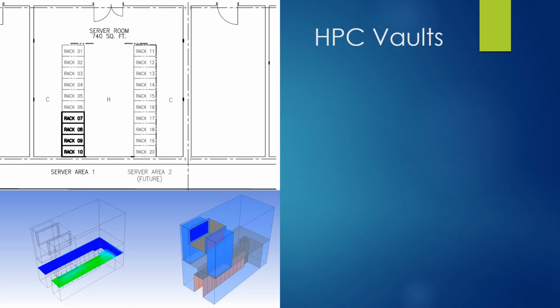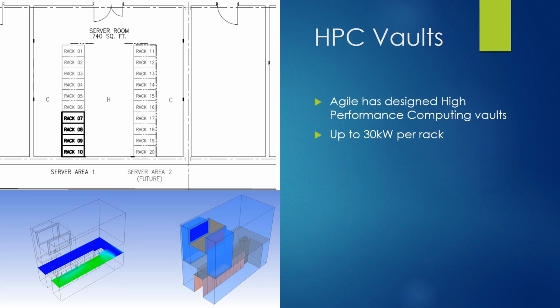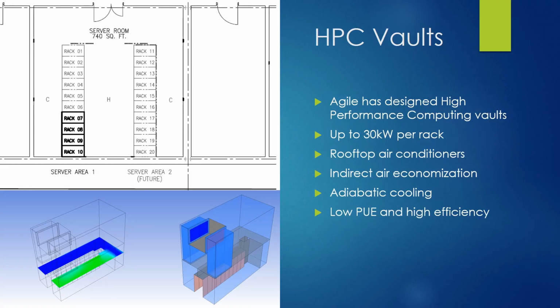But first, we'll talk about our HPC vaults, which use an air cooling system to cool up to 30 kW per rack. We do that by using rooftop air conditioners, because we can use outside air economization so that we can have very, very efficient systems. So we can use indirect air economization where we blow air past a heat exchanger and cool it down without using any refrigerant. Or adiabatic cooling where we drop down water over that heat exchanger to evaporate, which again greatly increases the efficiency. And to do that, we actually can see very low PUE and high energy efficiency.